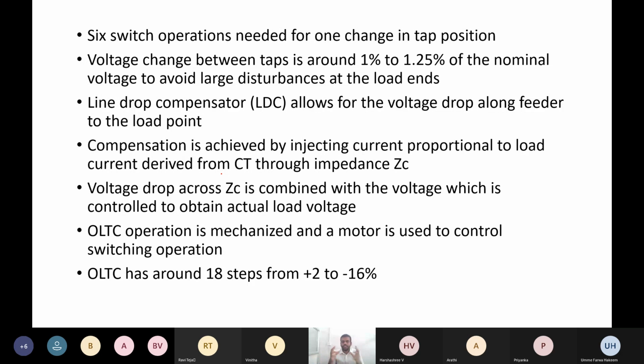So you can't straight away just go and change the tap positions. If you blindly change the tap position, what happens? The load ends will be heavily disturbed. That may sometimes lead to a collapse of the grid. Sudden variations in the loads, sudden fluctuations in the voltage or current lead to collapse of the grid, leading to blackout. So that's why we always have to keep in mind to protect the circuits. Protection of circuit is nothing but protection of our sending end or protection of our receiving end.